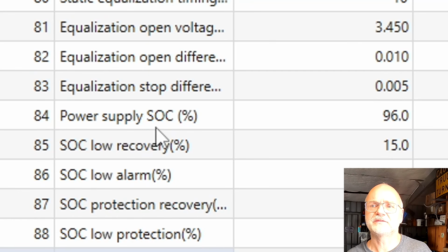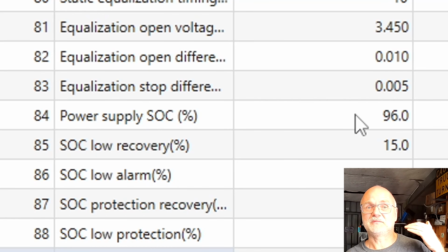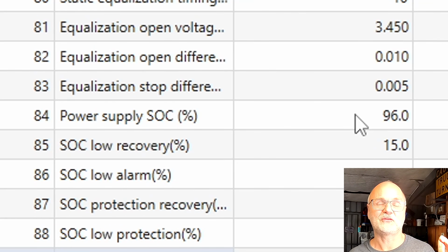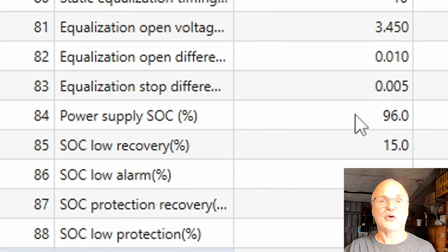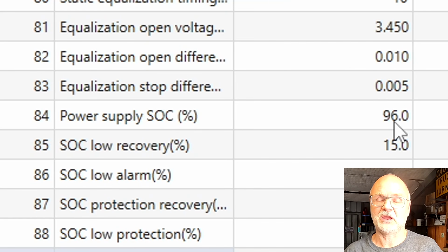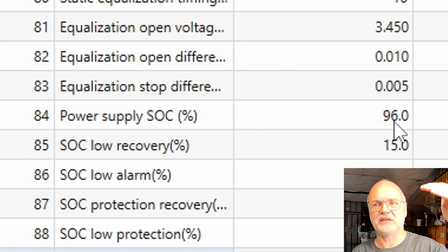Here it is, number 84, the power supply state of charge, sitting at 96%. In previous software versions and BMSs, this was called the gap charge function. What this does is charge your battery to 100%, then turn off the charge MOSFETs so no charge comes in until the battery reaches 96% state of charge. Then it turns the charge MOSFETs on again, charges to 100%, and the cycle repeats. This is just a setting you can adjust, even down to 90% if you want, and the battery would cycle between 100% and 90% all the time.